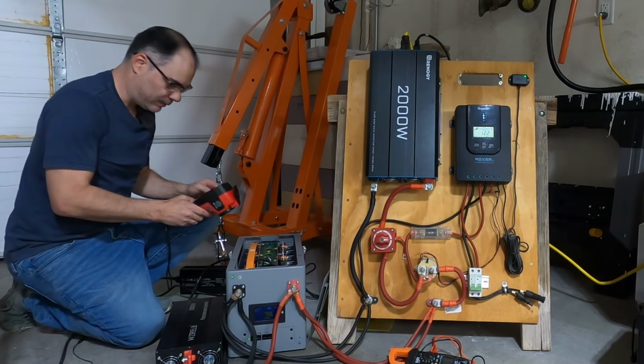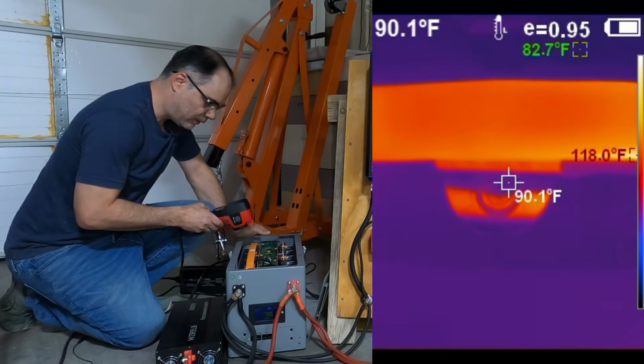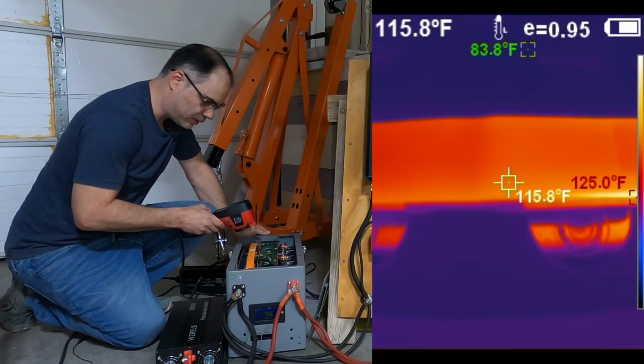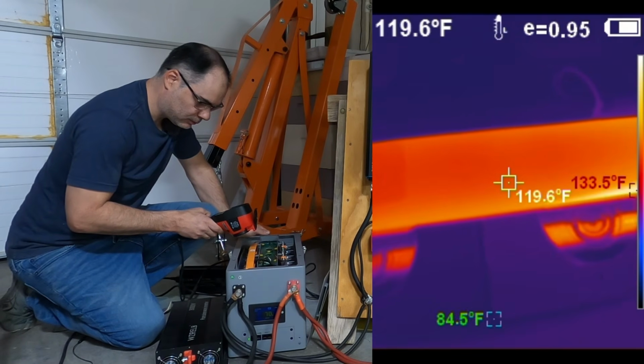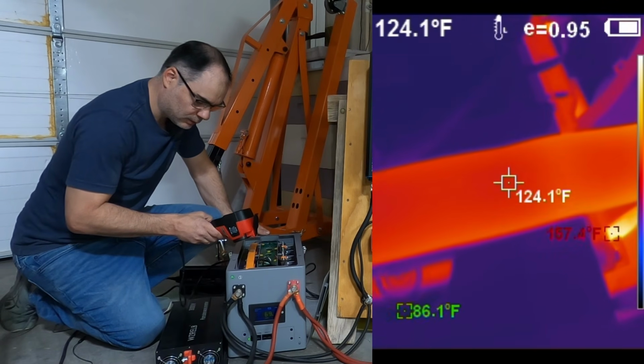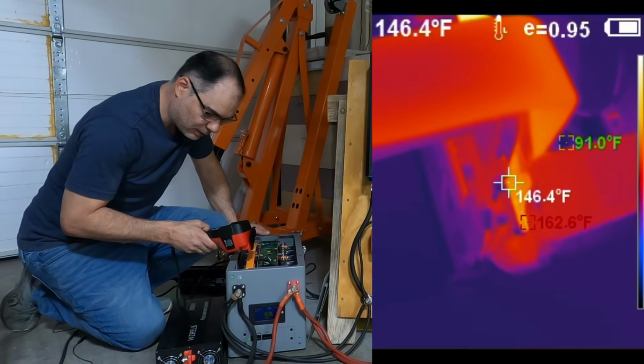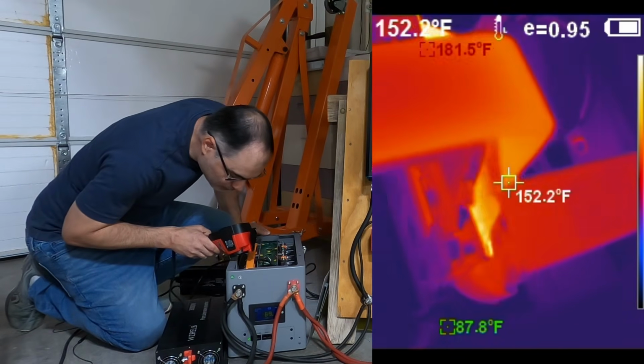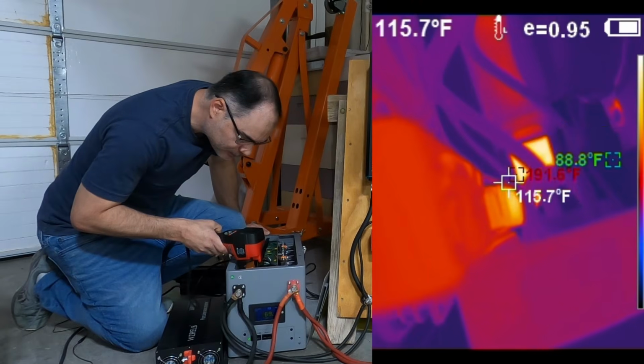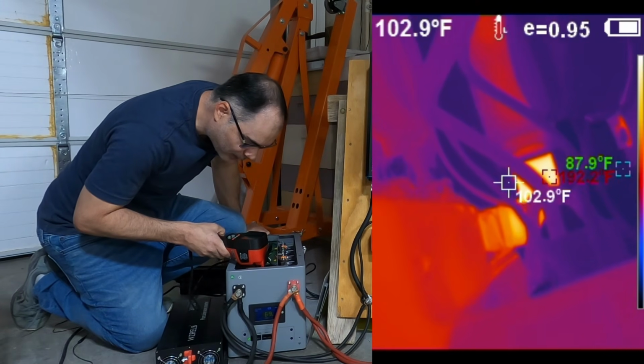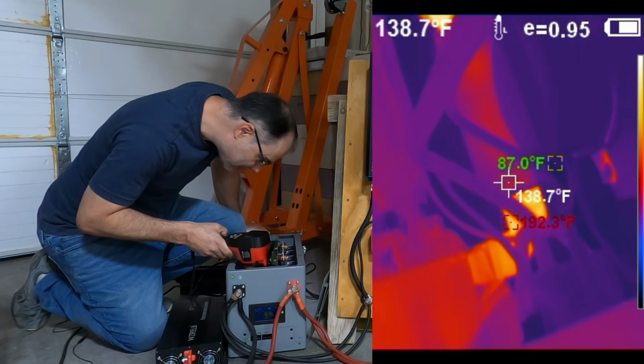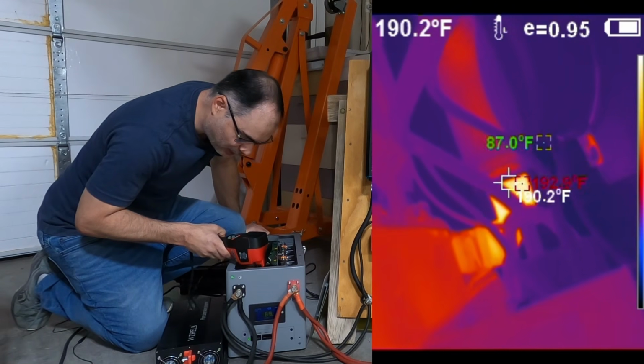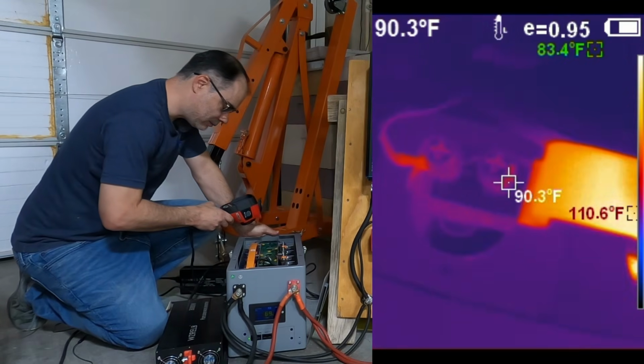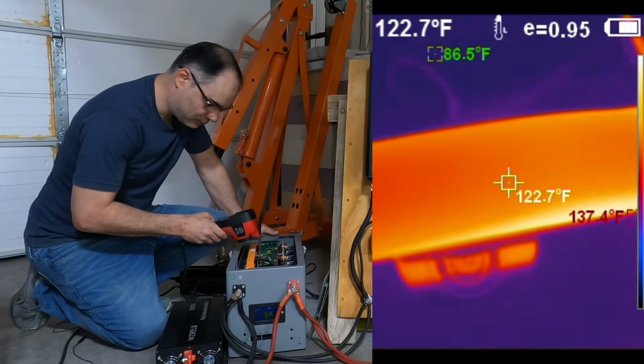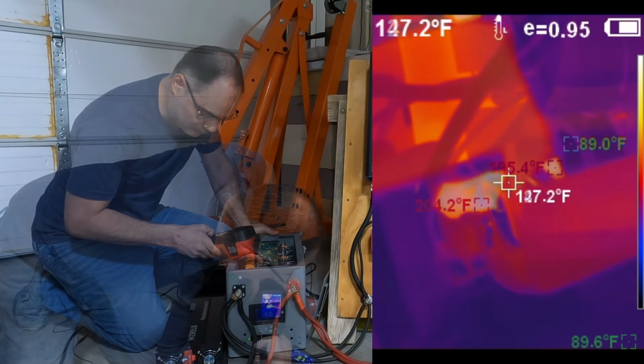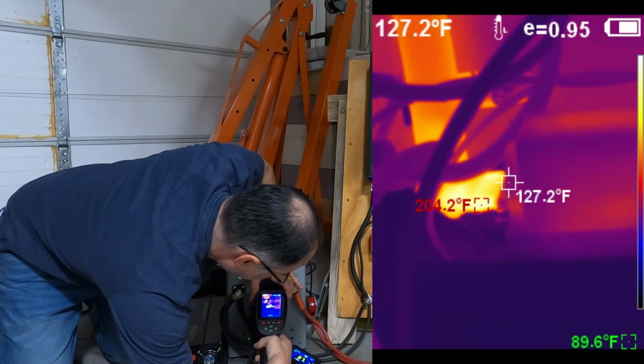So we're going to take a look at heat stress in the battery. You can see the bus bar is hitting about 125 degrees. 130 over there. Wow, 100, what is that? 162. Well, 192. Is that on the fuse? I think that's on the fuse terminal. 192. Wow. Man, 200 degrees on that fuse. 204.